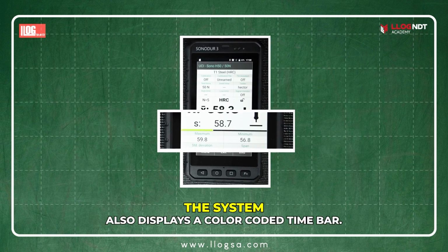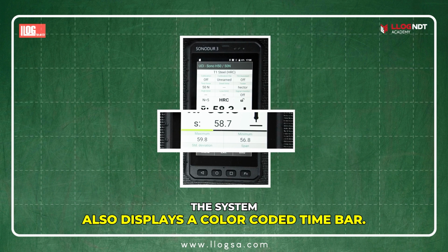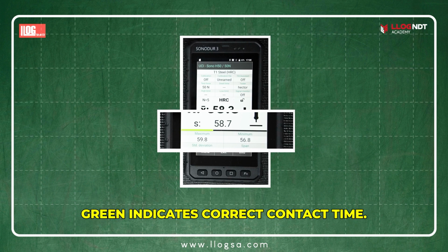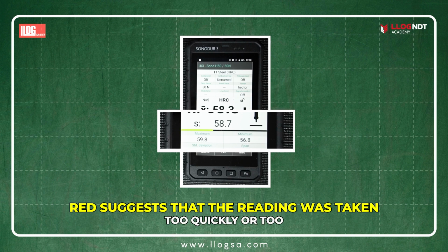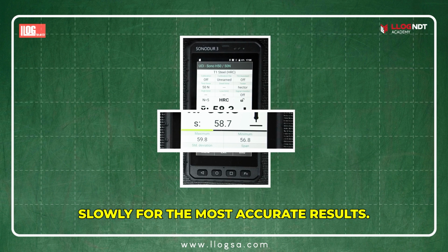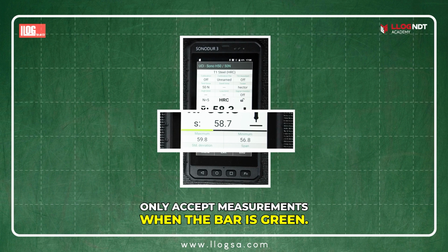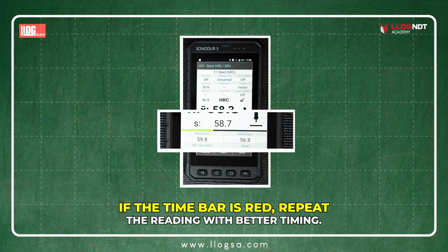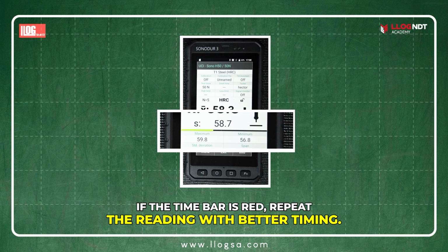While taking readings, the system also displays a color-coded time bar. Green indicates correct contact time. Red suggests that the reading was taken too quickly or too slowly. For the most accurate results, only accept measurements when the bar is green. If the time bar is red, repeat the reading with better timing.